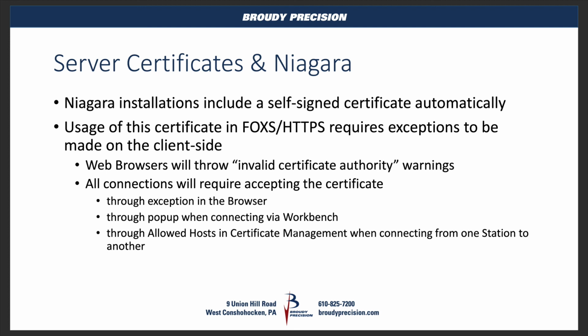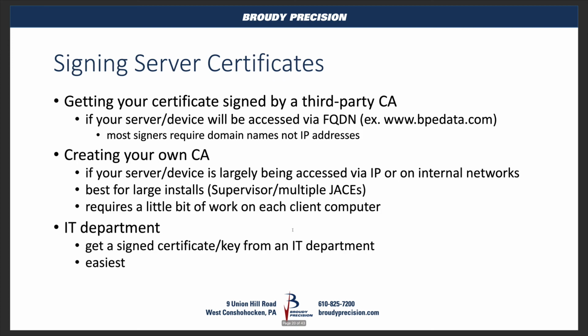I think most users of Niagara 4 have probably run into this error message before. So in our browser, we have to pass through that exception. When you're connecting through Workbench, you'll get a pop-up. And if you're connecting from station to station, you have to go into your allowed hosts in the certificate manager of your platform and allow those connections to happen, or allow those hosts.